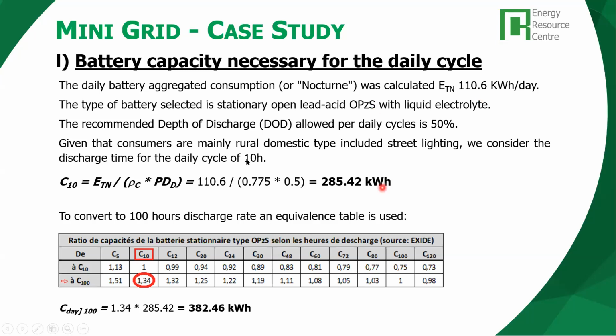So we use the formulas, if you remember, from the battery sessions I gave you. We have the total energy that needs to be stored in the batteries divided by the efficiency in the consumption and the depth of discharge. We end up having a total battery sizing need of 285.4 kilowatt hour capacity. That is a capacity for a 10 hour period. Also remember what we said in the battery technology session. The capacity of batteries depends on the period of discharging we are going to use for this battery. Normally, when we approach the quotation of batteries, we use the capacity C100 or capacity C20. This is something that has to be indicated in the specifications of the batteries.